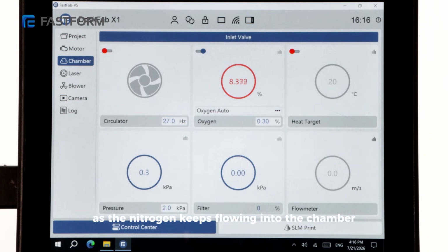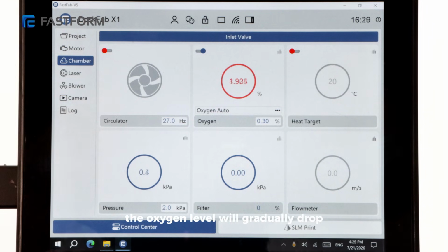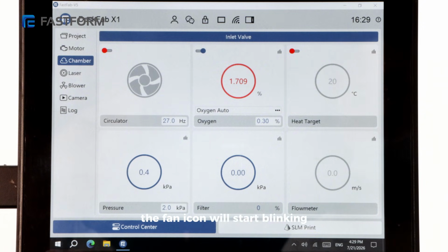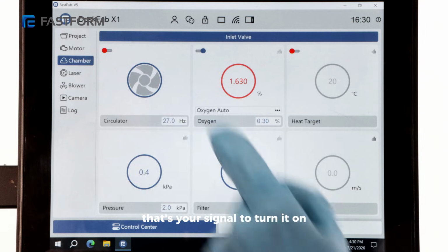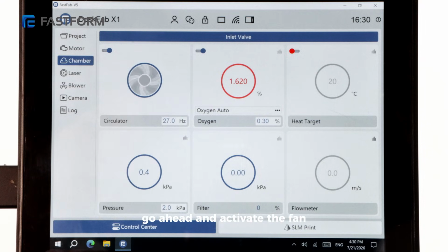As the nitrogen keeps flowing into the chamber, the oxygen level will gradually drop. Once it falls to around 1.7%, the fan icon will start blinking. That's your signal to turn it on. Go ahead and activate the fan.